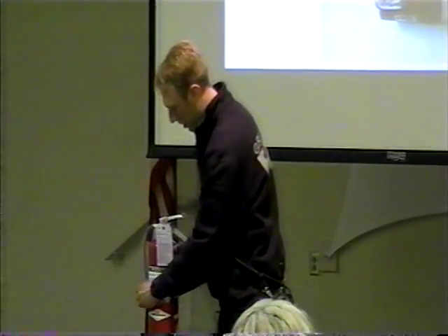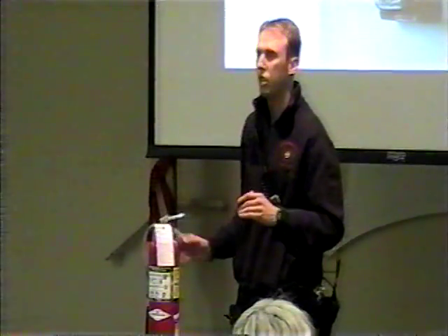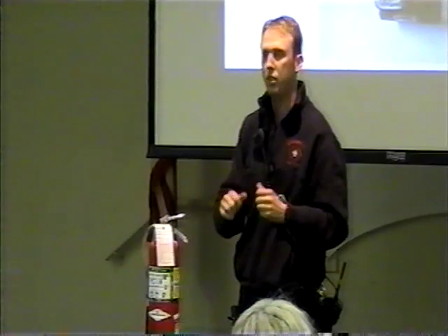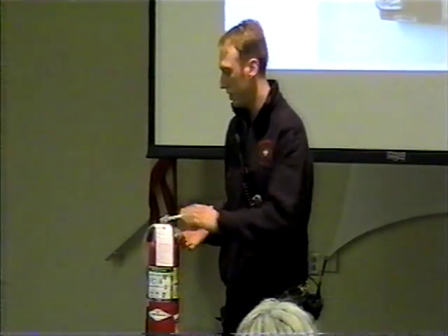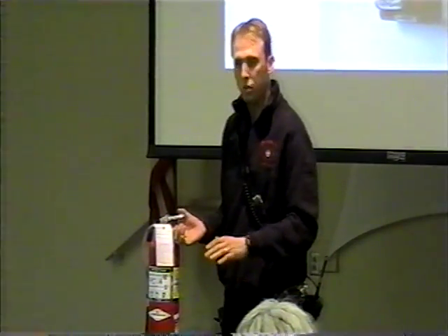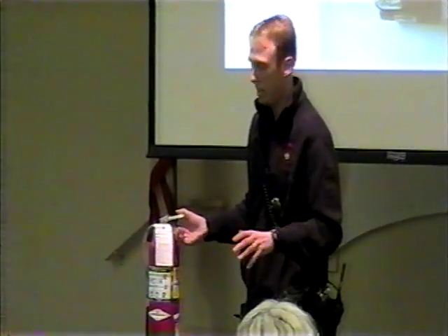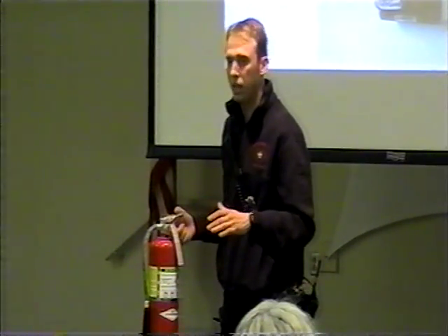Now before even going into a fire, you want to analyze it. Is it an area where you can get in and get out quickly? Because you always want to be between the fire and your exit, just in case it does get so bad you can get out right away. So you want to analyze the fire. Is it growing too fast for your capabilities? Like I said, this will only last about 30 seconds, and it can only properly extinguish a wastebasket fire.